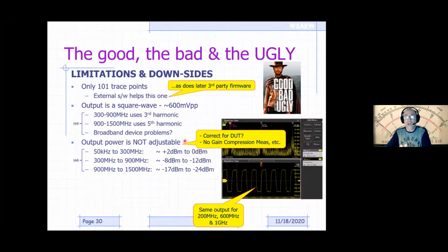So again, is that output power correct for the device you're measuring? For an antenna, for a passive filter, for things like that, you don't care, right? But if you're developing an active circuit, like an active filter, an amplifier, a buffer, then it may matter, and you can't adjust it. Okay? So if you need higher power, you have to throw an amplifier in there. If you need lower power, you have to throw an attenuator in there. But because you can't adjust the power, you can't make some common RF measurements like gain compression measurements and things like that.